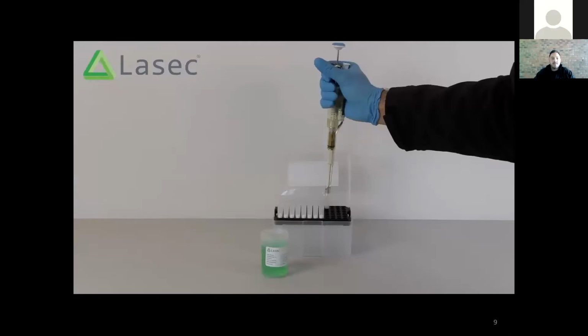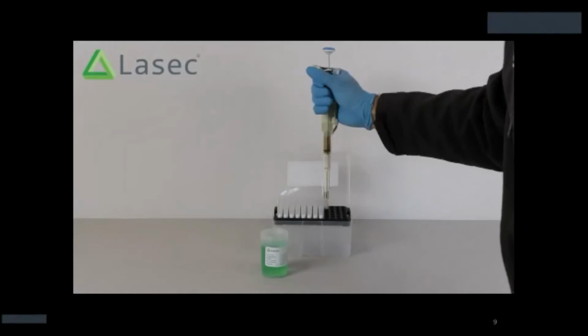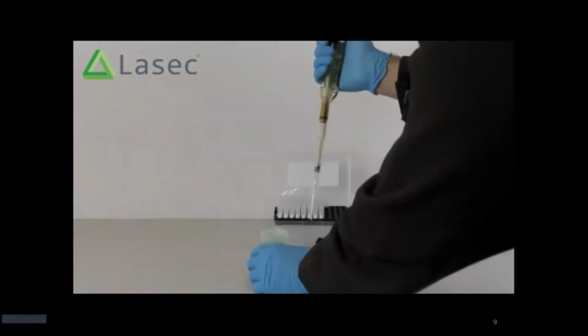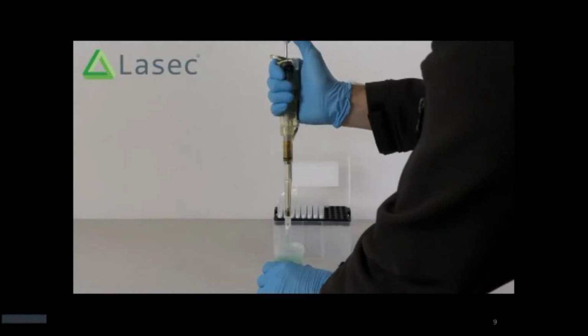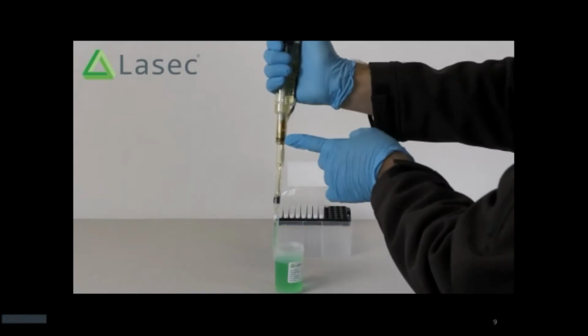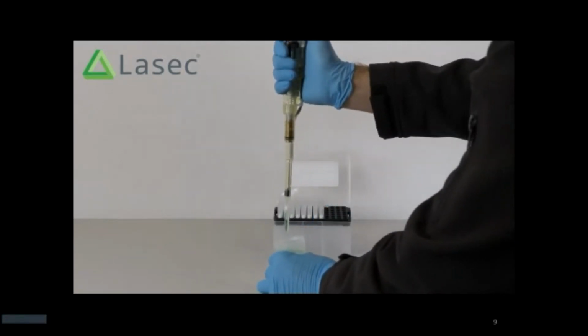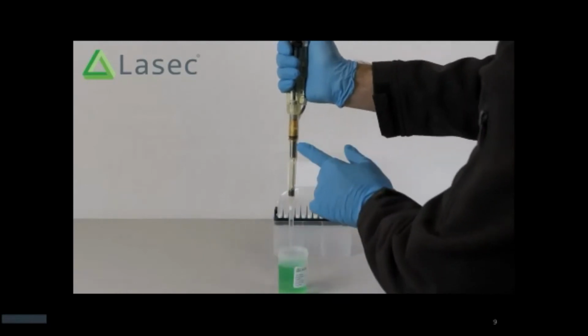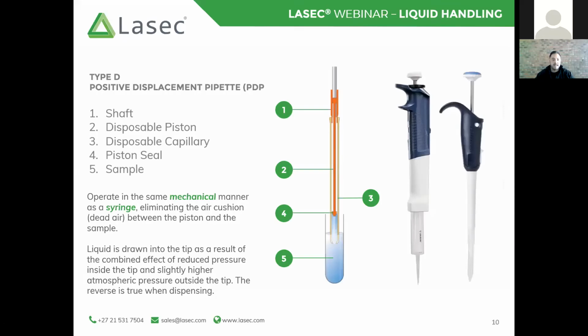I will now play a video just showing you a bit of the functions of an air displacement pipette and walking through what I am doing. So basically, I'm preparing the aspiration. As you can see, the plunger inside the pipette, when I prepare for that aspiration, depresses down into the tip holder. As I dispense the liquid, it presses down again. And you can see that there was always an air gap between that piston and the sample itself. So that is the main principle of the air displacement pipettes. However, like I said, because of the elastic properties of that air inside the pipette, there are a number of limitations. To overcome some of those limitations, they have designed positive displacement pipettes. So what is a positive displacement pipette and how does it differ?